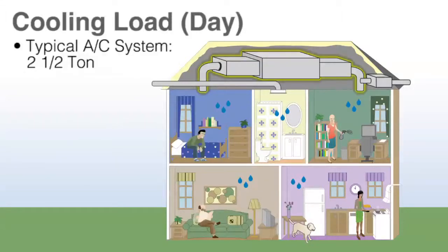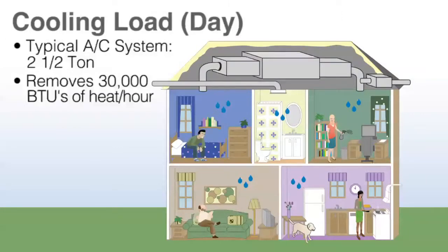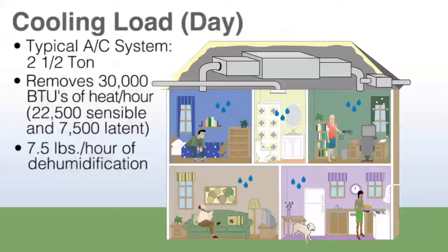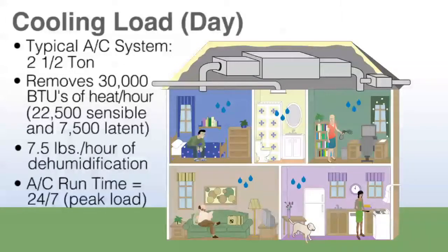A two and a half ton AC would typically be recommended for a high-quality home of this size. Properly set up and sized, this would remove 30,000 BTUs of heat per hour — 22,500 BTUs would be sensible heat and 7,500 BTUs would be latent, which is moisture removal. This amounts to 7.5 pounds of dehumidification per hour. If the AC is running total time, this matches the amount of water that the AC would remove. Ideally, an AC is capable of maintaining 75 degrees and 50% relative humidity during peak load conditions.